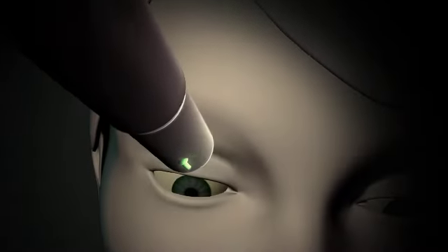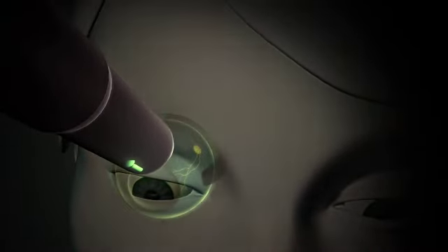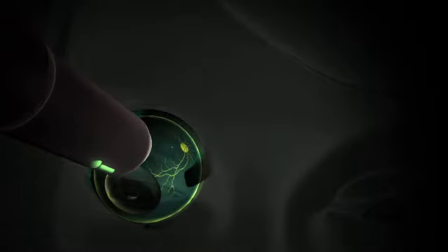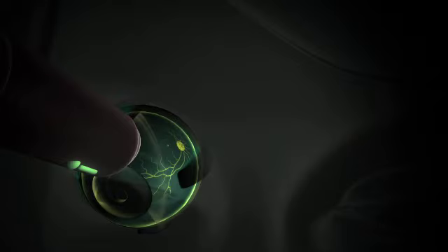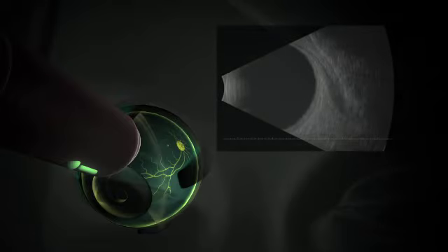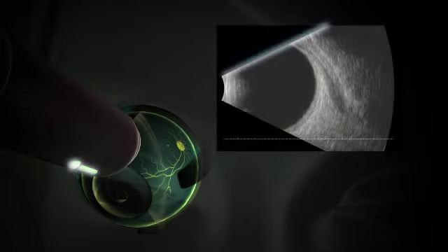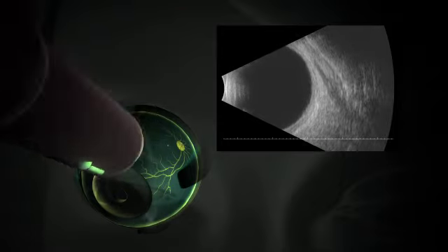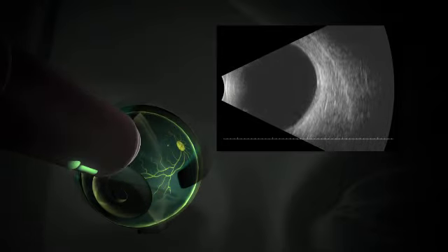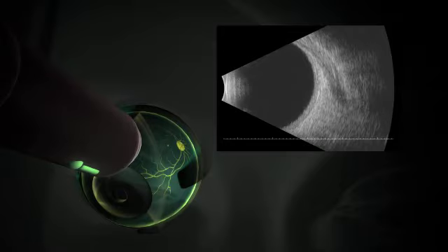If you want to cross-reference yourself, you simply have to take the probe and rotate it so it is located close to the cornea, which would be a 90-degree turn, and you will now achieve a sagittal cut. The top of the screen, sagittally, will be close to the angle of the cornea and iris, and the bottom of the screen will be close to the back wall of the eye and the optic nerve.